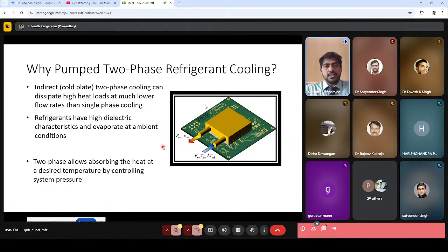Cold plate two-phase cooling can dissipate high heat loads at much lower flow rates than single-phase cooling, which means it can be more energy efficient. The refrigerants have high dielectric characteristics and evaporate at ambient conditions. Two-phase cooling also allows absorbing heat at a desired temperature by controlling the system pressure.